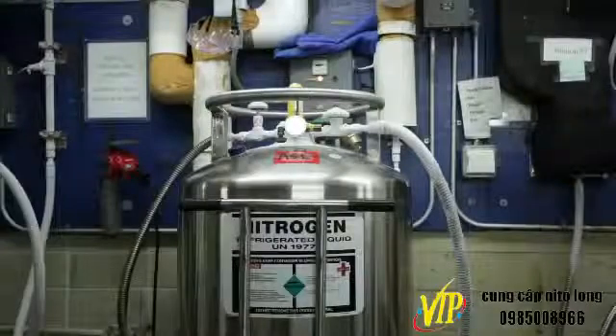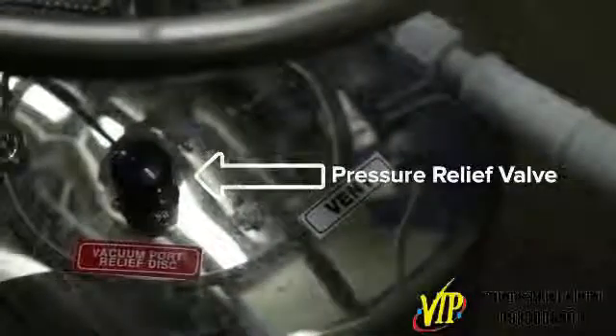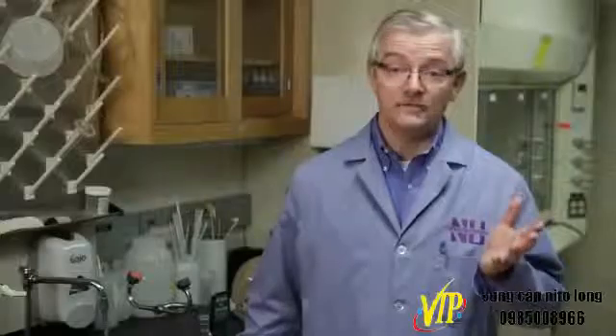Consult the tank manufacturer's operating manual and get familiar with the functioning of the tank valves and piping circuits. A typical liquid nitrogen tank has multiple pressure relief valves. Never obstruct, block, cover, or tape a pressure relief valve. If your cylinder vents loudly through the relief valve, is cold to the touch, or has frost buildup around the pressure relief valve, leave the room and contact emergency services.